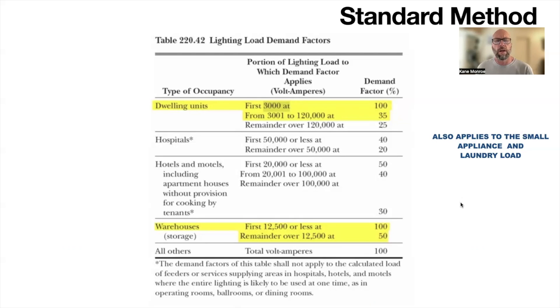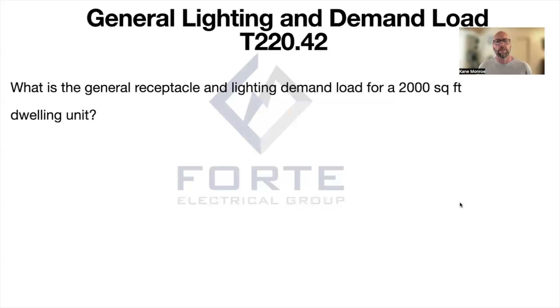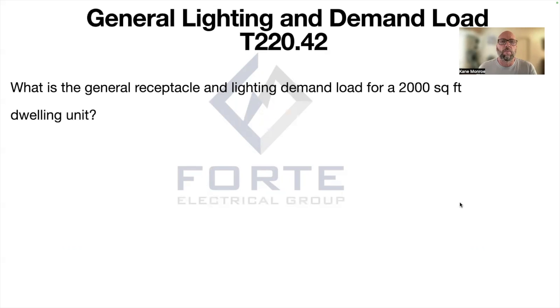So let's get started. What is the general receptacle and lighting demand for a 2,000 square foot dwelling unit? We know we have 2,000 square feet, and according to the code we have to allow 3 VA per square foot, so we take 2,000 and multiply it by 3, which gives us 6,000 VA.